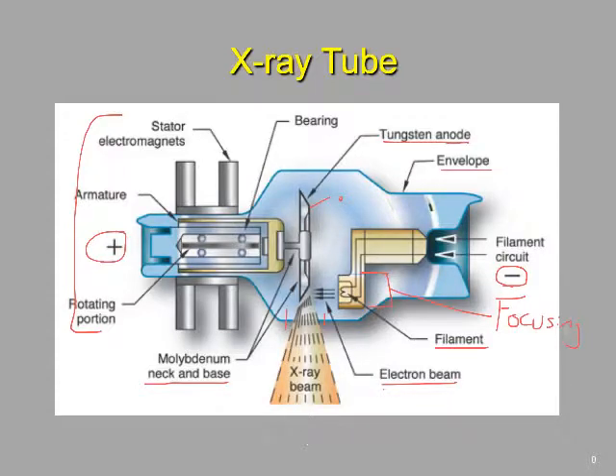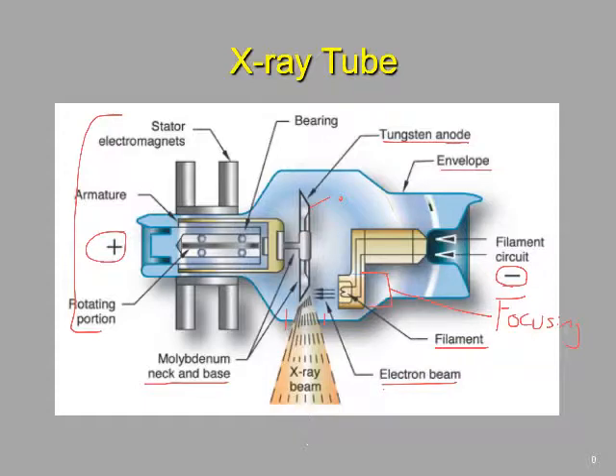On the anode side we have a contained system whose large parts are the stator and the rotor. The stator produces electromagnetic pulses that cause the rotor to rotate. There is no mechanical connection between the stator and the rotor — the glass envelope covers this entire tube — so we are causing movement to occur through glass using electromagnetic pulses.